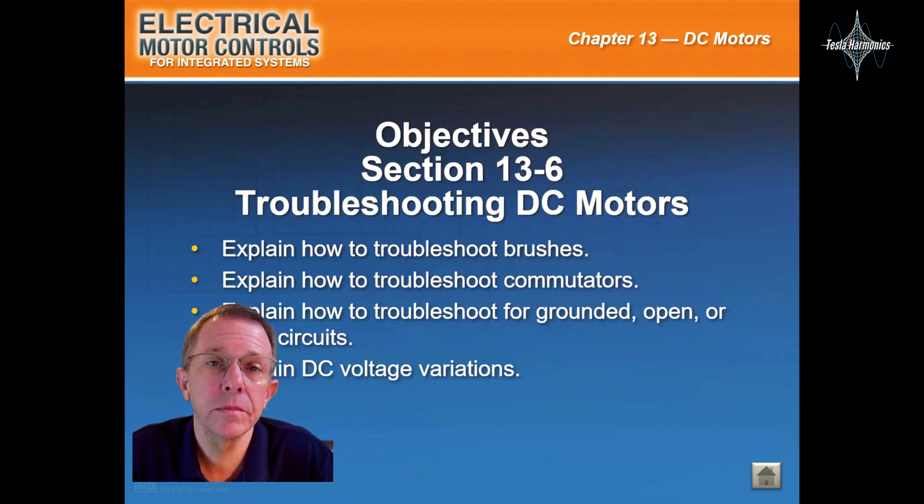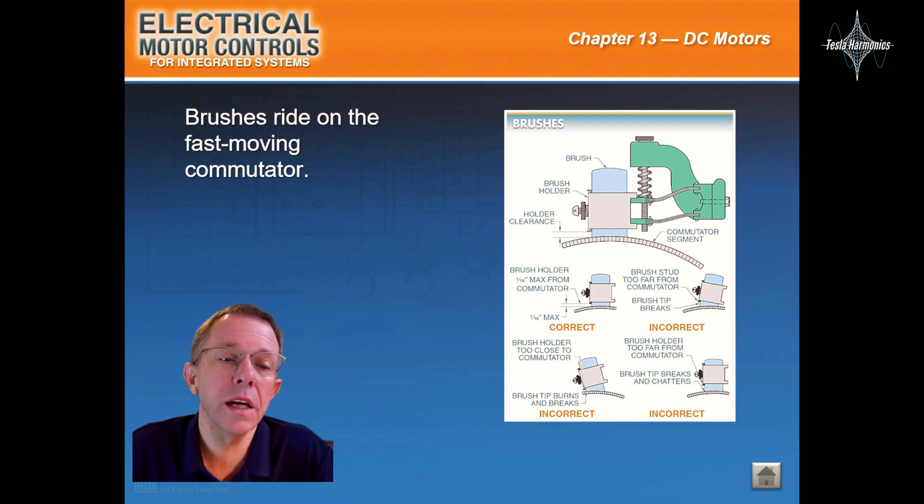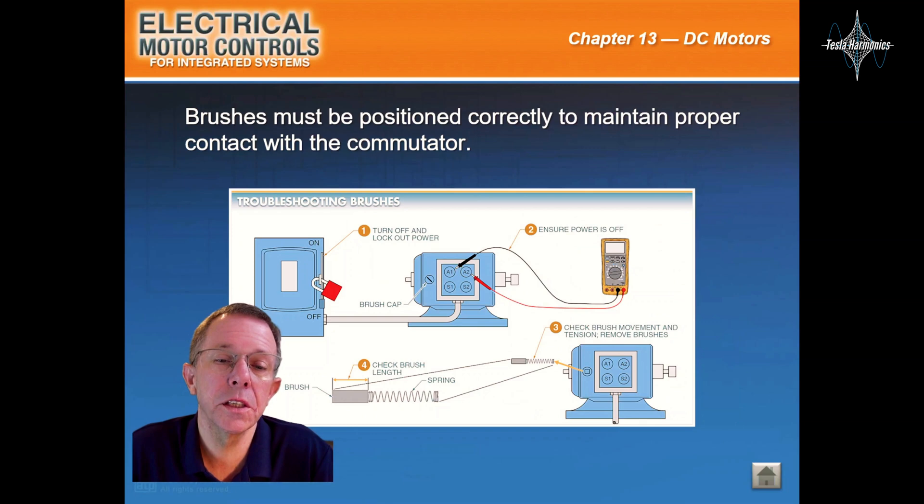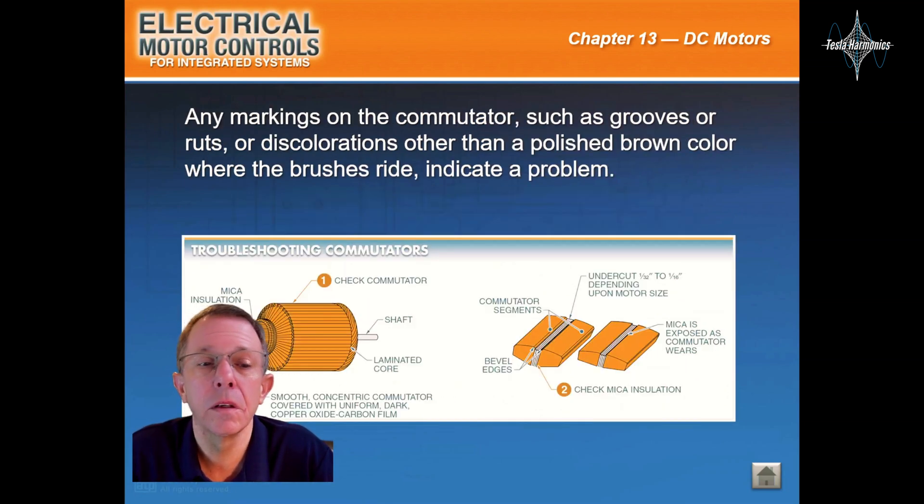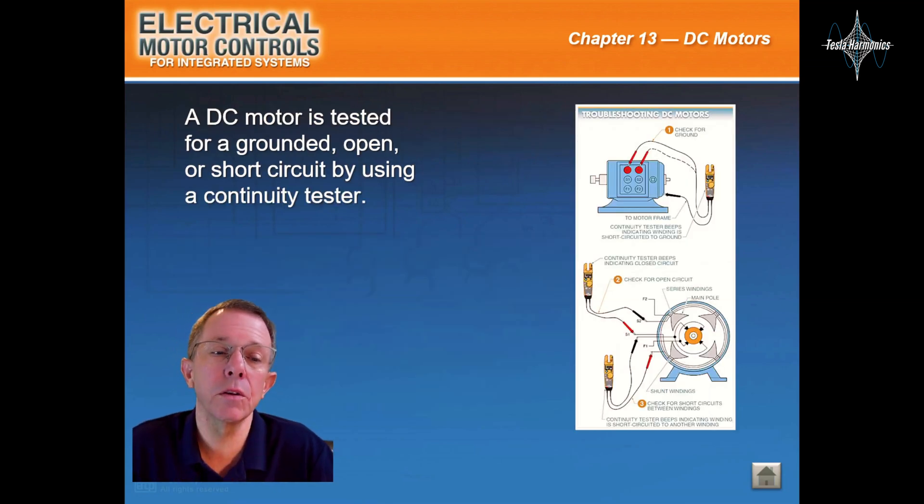Troubleshooting DC motors: Brushes ride on the fast moving commutator. Brushes must be positioned correctly to maintain proper contact with the commutator. Any markings on the commutator such as grooves or ruts or discolorations other than a polished brown color where the brushes ride indicate a problem. A DC motor is tested for a grounded, open, or short circuit by using a continuity tester.